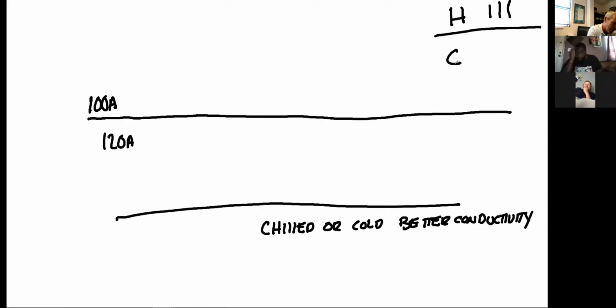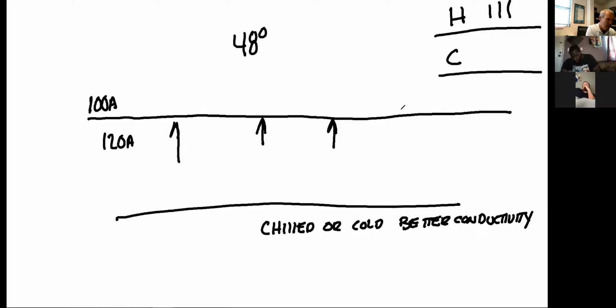So back to the original question: what's more beneficial in my system, heat or cold? Cold. Remember that 48-degree difference we had to make up? It's actually offset somewhat by being in cold temperatures for the system itself. Even transformers, when they're in a cold environment, will actually do better in kVA when they're chilled down and gotten real cold.